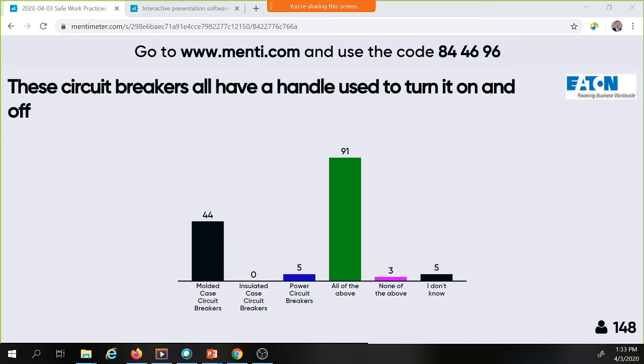Yep, it's not all of the above. Those on the 44 in the molded case circuit breaker world said molded case circuit breakers have a handle to turn them off. You are correct. Molded case circuit breakers will all have a handle that you will use to turn it on and off. Power circuit breakers and insulated case circuit breakers all have a push button that you would use to turn it on and off.